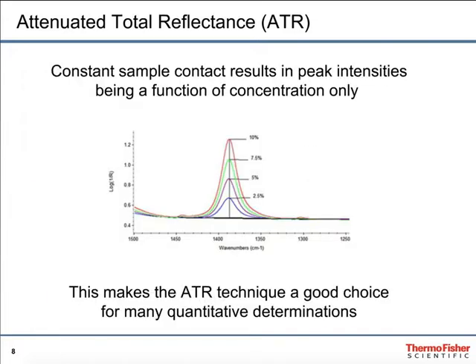One of the frequently asked questions about ATR is whether it can be used in quantitative analyses, and the answer generally is yes. If the sample is either a liquid — in which case it makes good contact with the surface — or if it's a solid and we can generate reproducible pressures to interact with the crystal, then the peak height becomes a function only of the concentration of the materials. You can calibrate the ATR and use it, so it's very good for many quantitative applications.